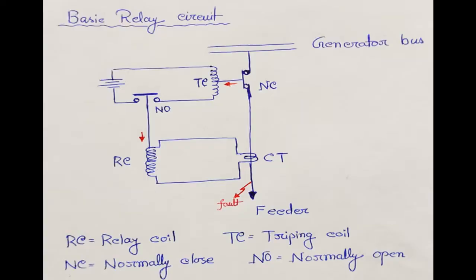So now let's understand the basic operation of the relay circuit. Here, this is the generator bus bar, and from the generator bus bar, the feeders are connected, and the function of the feeder is to bring the power from the generator bus bar to the load center. Load centers are connected here. As this one feeds the electricity from the generator bus to the load center, that's why it is called the feeder. Now, this feeder is controlled by this switch, but this switch is normally closed.